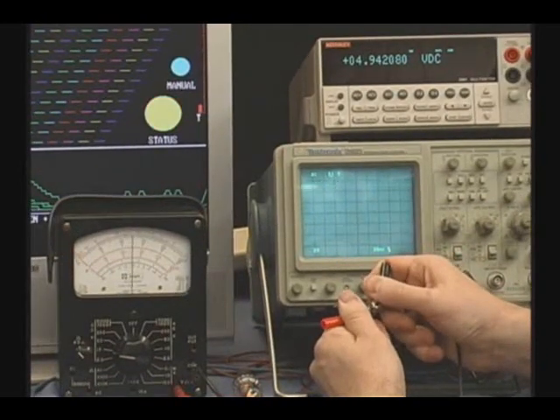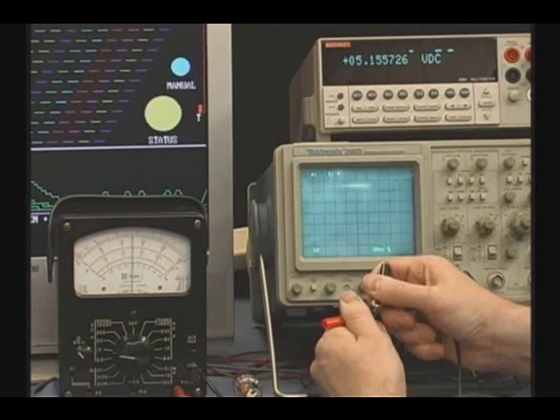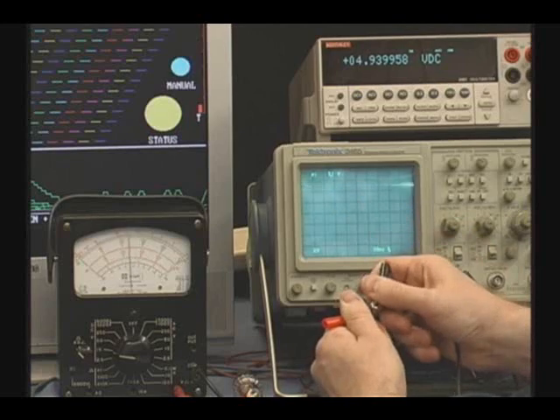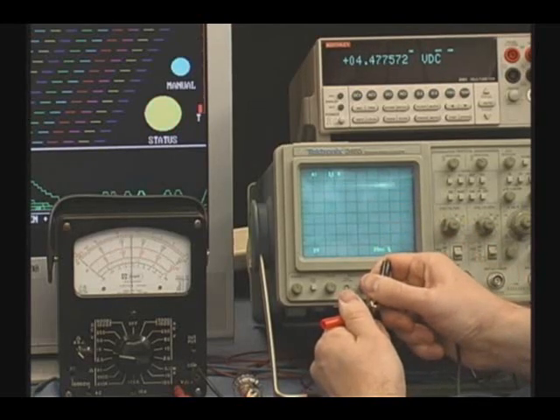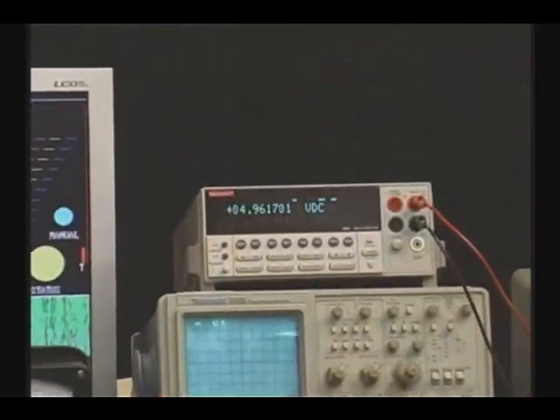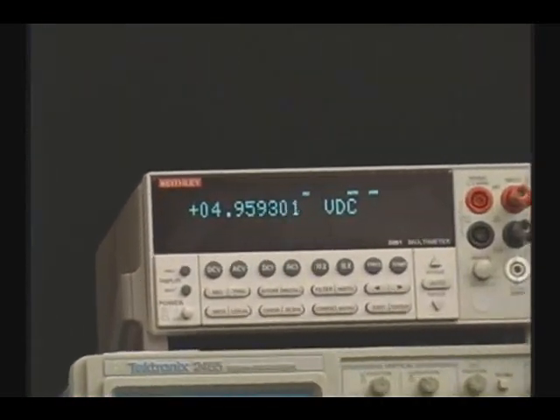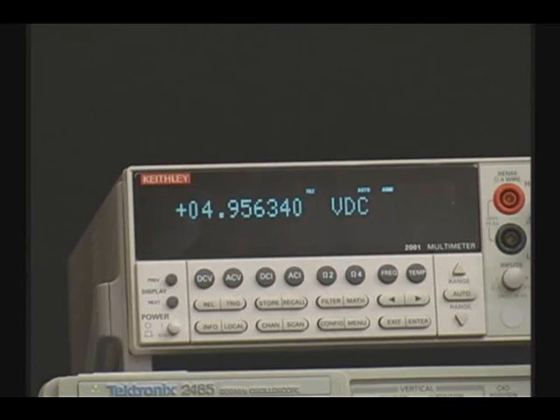The programmable digital multimeter is the backbone of the testing industry. As you can see, the meter has a difficult time tracking the voltage changes that I am creating. This difficulty is due to the high levels of digital averaging that are employed in the meter to enable it to reach its high levels of accuracy.